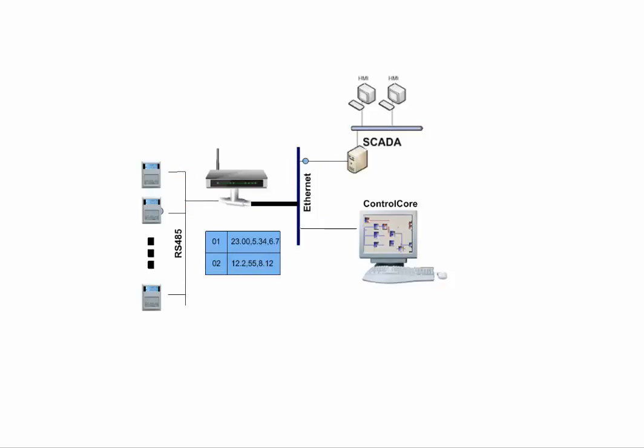With the network controller, the scanning of devices and responding to outside requests are strictly separated. The network controller takes care of scanning all the required devices, ensuring peer-to-peer communications work while keeping a record of all the devices' values. Outside applications make a request and immediately get a response, because the network controller doesn't have to relay the request down the slow RS-485 line. It simply responds using the values it obtained with its last scan.